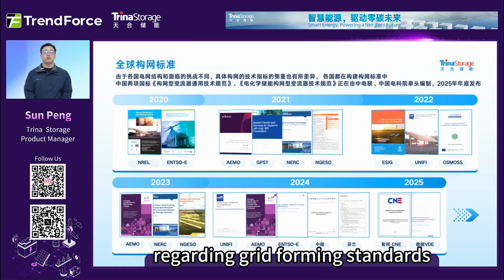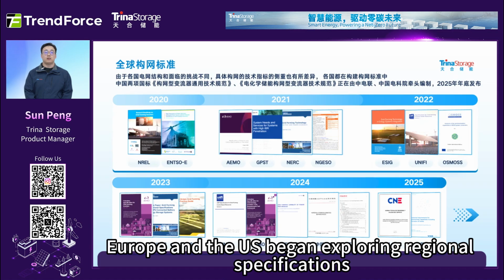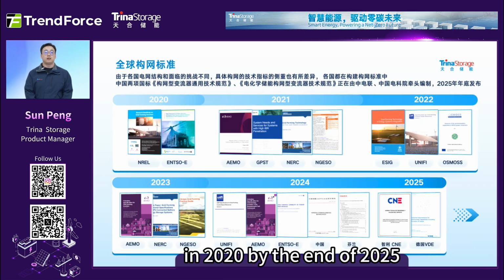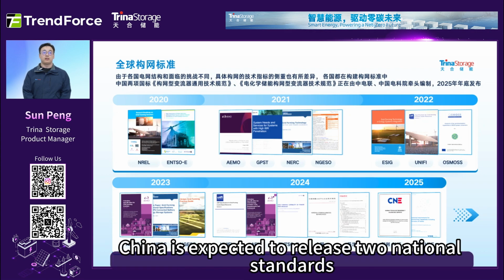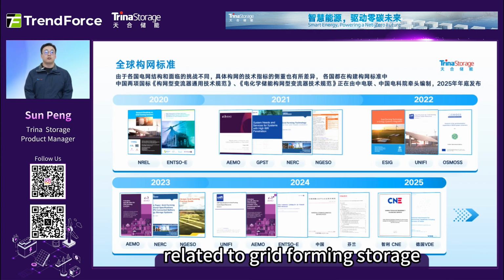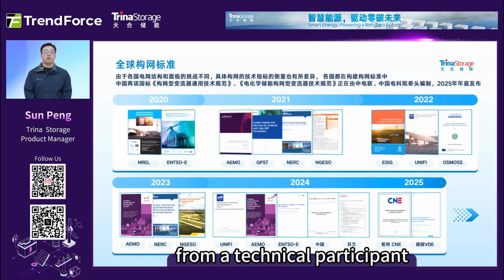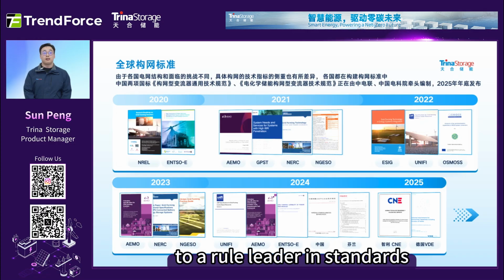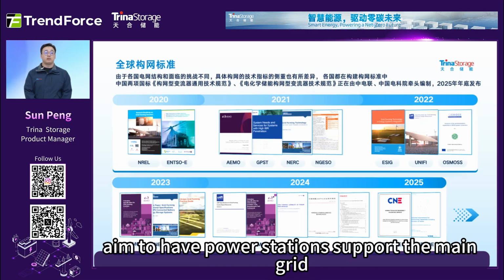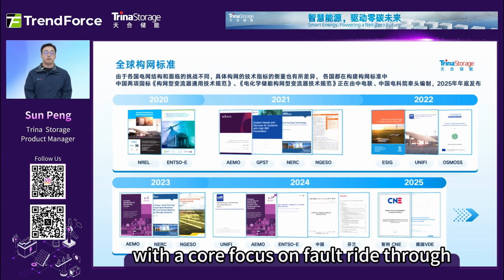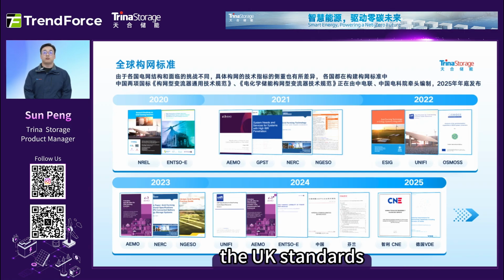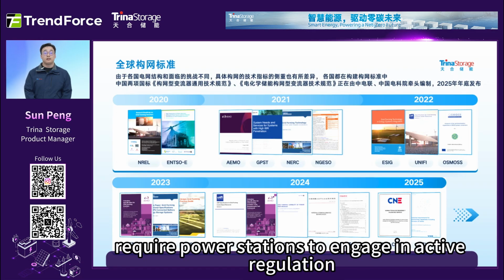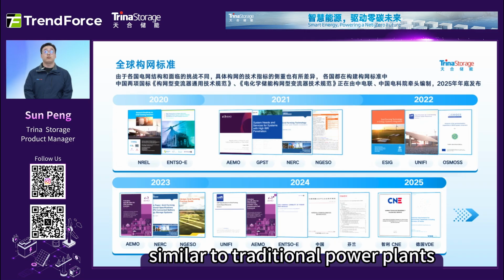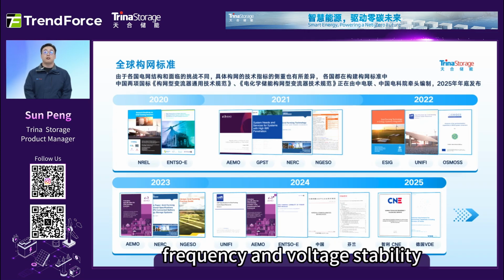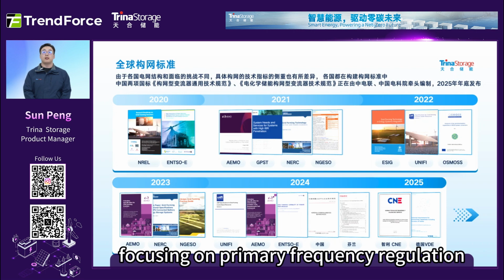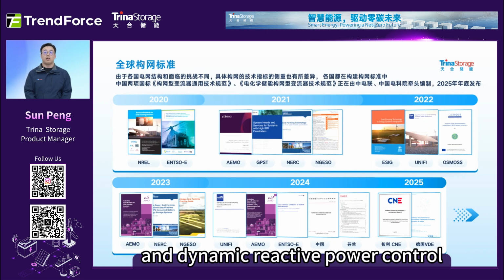Regarding grid-forming standards, Europe and the US began exploring regional specifications in 2020. By the end of 2025, China is expected to release 2 national standards related to grid-forming storage. This marks China's transition from a technical participant to a rule leader in standards. China's standards aim to have power stations support the main grid, with a core focus on fault ride-through and reactive power support. The UK standards require power stations to engage in active regulation, similar to traditional power plants, maintaining system-wide frequency and voltage stability, focusing on primary frequency regulation and dynamic reactive power control.